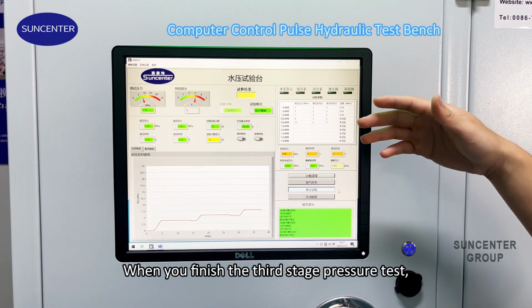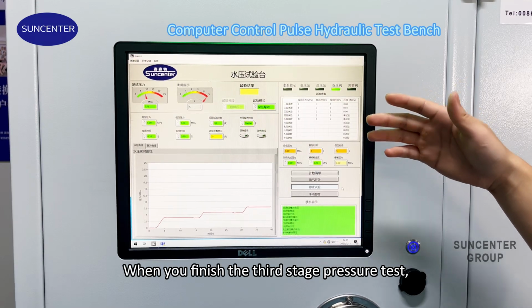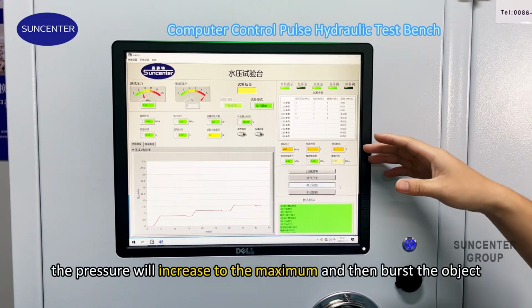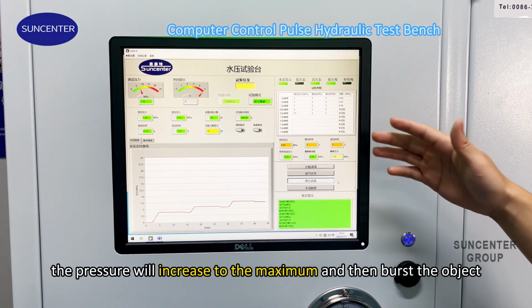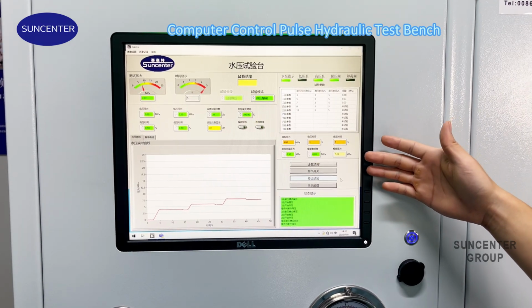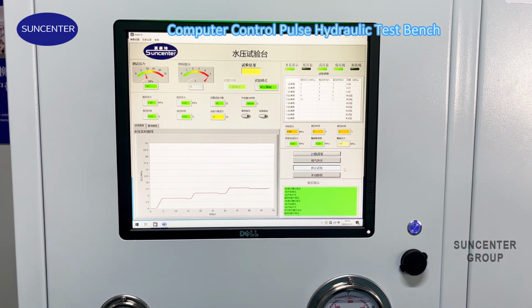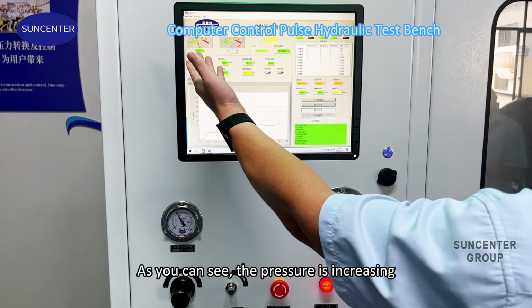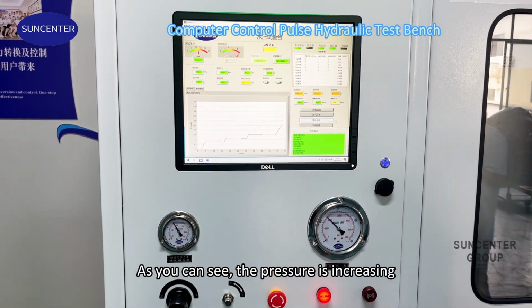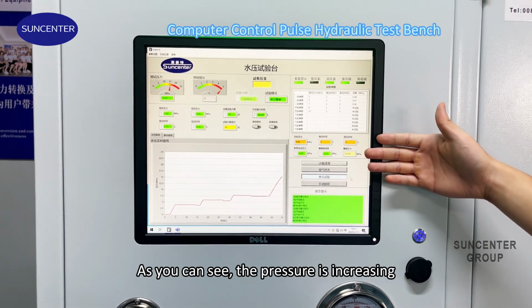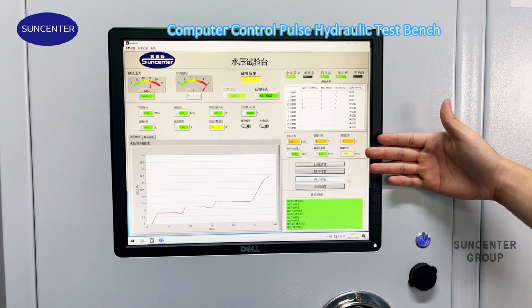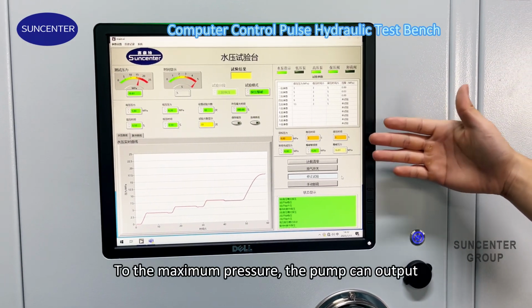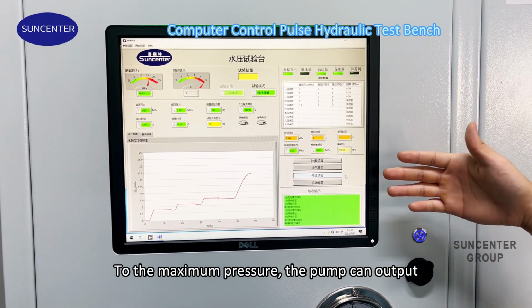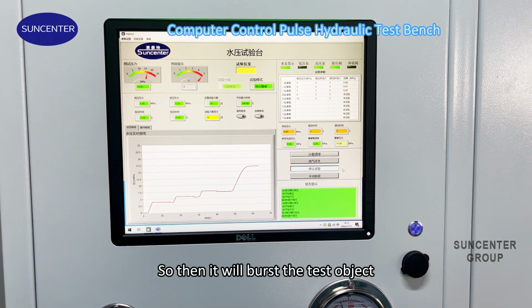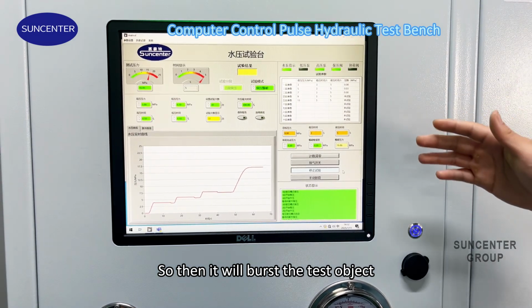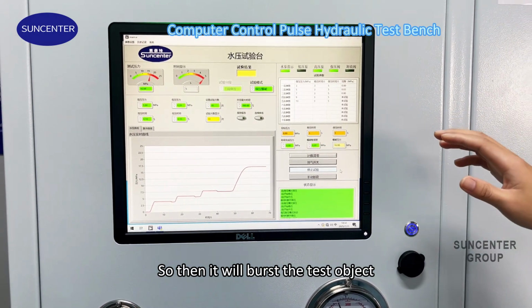When you finish the third stage pressure test, the pressure will increase to the maximum and then burst the object. As you can see, the pressure is increasing to the maximum pressure the pump can output. So then it will burst the test object.